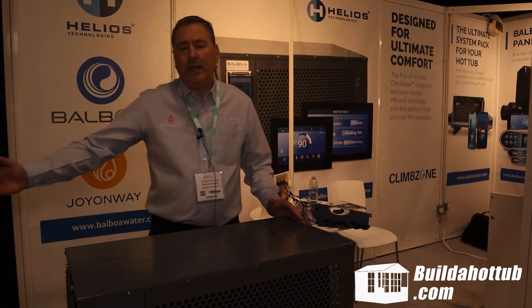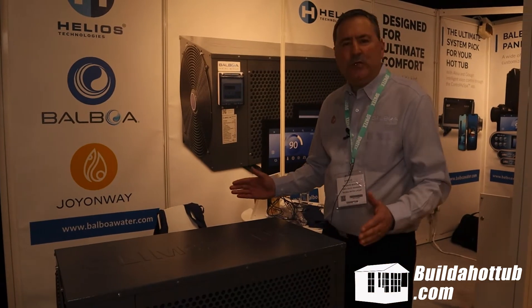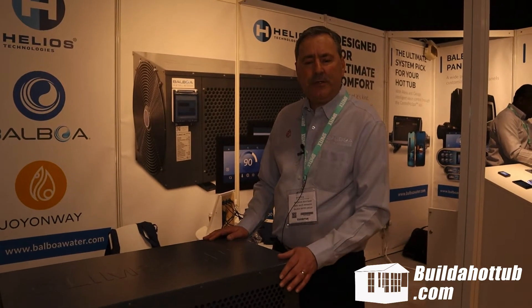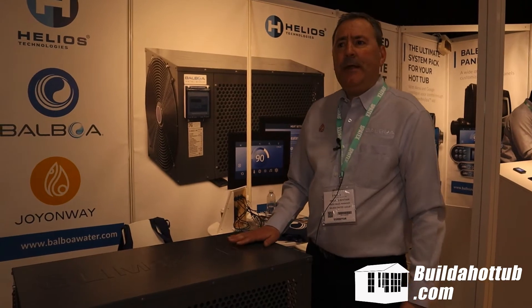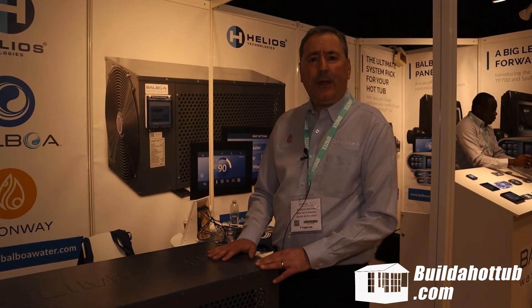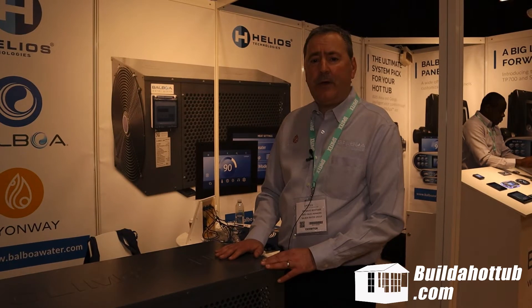The important part is just to make sure you have sufficient clearance. Away from the fan would be two meters, then you have about a 20-inch clearance at the back and around four or five inches towards the front. Heat pumps are becoming very popular now. With the rising cost of electricity and the impact on the planet, heat pumps are going to become a very popular item.